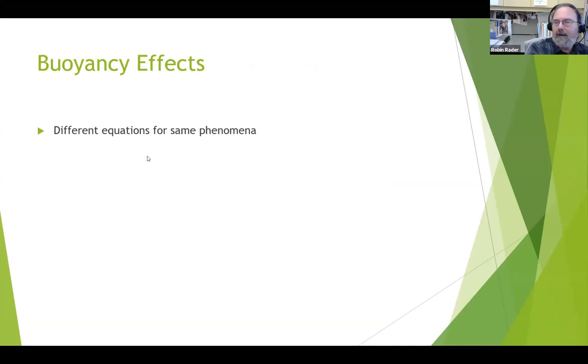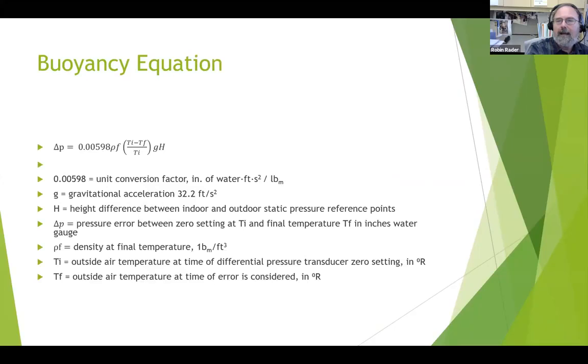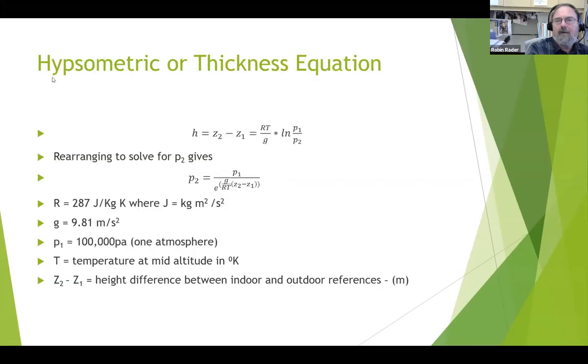Different equations for the same phenomena. So I'm going to talk about equations you can use to get an accurate sensing condition, even if you have your sensors at two different elevations. This equation below is the buoyancy equation that you can find in ASHRAE, and it can show you what stack effect pressures you will have at different outside air temperatures. This equation here is called the hypsometric equation, and it is an equation that meteorologists use.